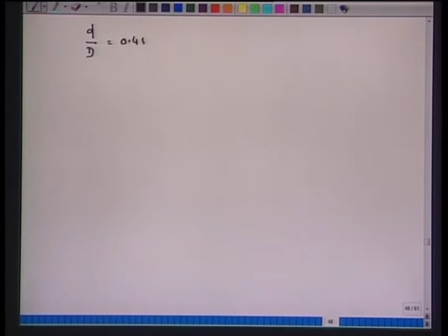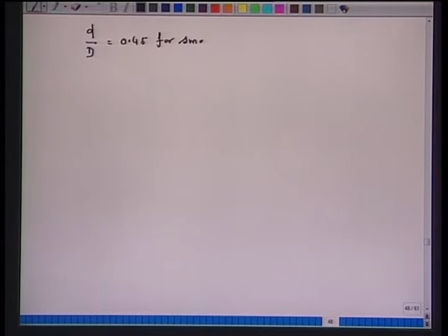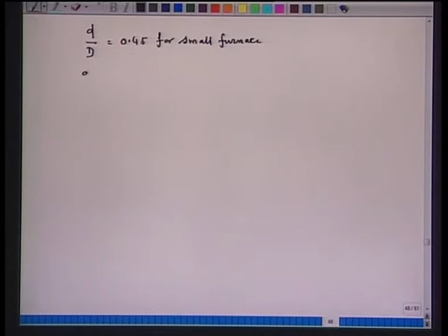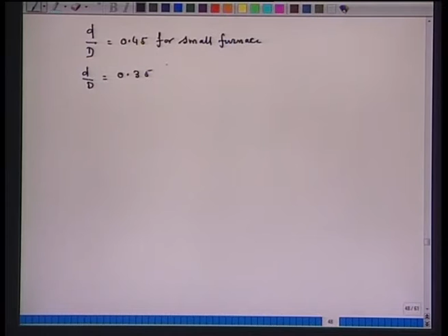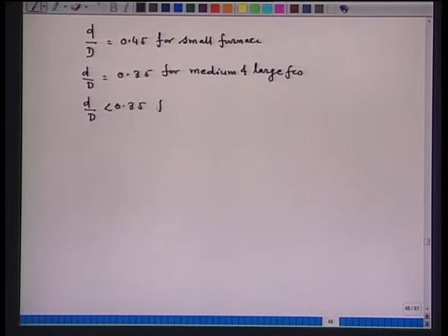If d is the pitch circle diameter of the electrodes, where all 3 electrodes are arranged at the apexes of an equilateral triangle, and D is the bath diameter, then d by D is approximately equal to 0.45 for small furnaces. For medium and large furnaces, d by D is equal to 0.35, and d by D less than 0.35 is preferred for superpower furnaces.